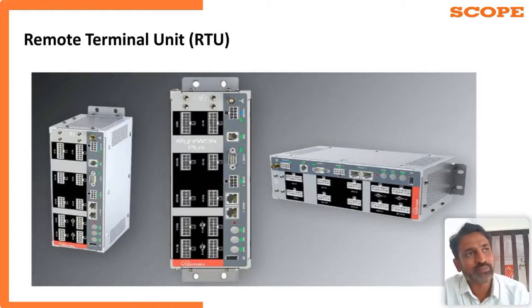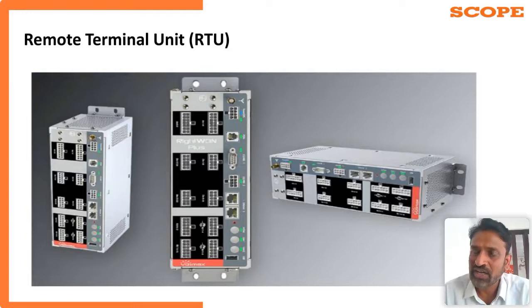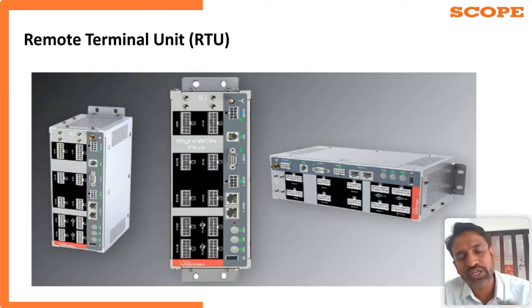But when it comes to an old system or existing substation, where you want to turn those existing substations into an automation system, if you want to give an automation system to a particular substation or a particular group of substations, what you need to do is either completely replace the existing relays with numerical relays. If it is already having numerical relays, that is okay.